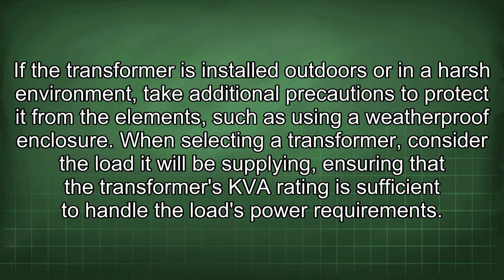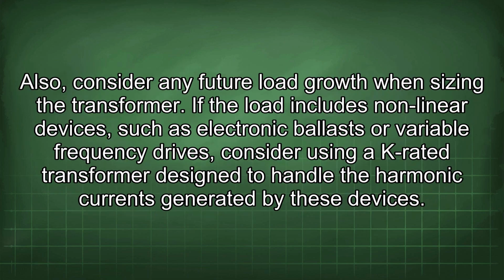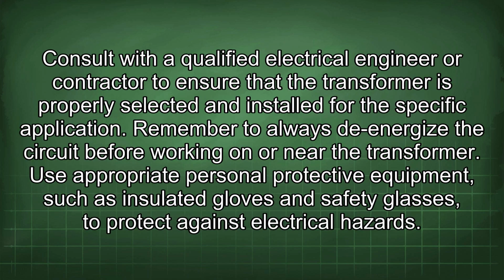When selecting a transformer, consider the load it will be supplying, ensuring that the transformer's kVA rating is sufficient to handle the load's power requirements. Also, consider any future load growth when sizing the transformer. If the load includes nonlinear devices, such as electronic ballasts or variable frequency drives, consider using a K-rated transformer designed to handle the harmonic currents generated by these devices. Consult with a qualified electrical engineer or contractor to ensure that the transformer is properly selected and installed for the specific application.